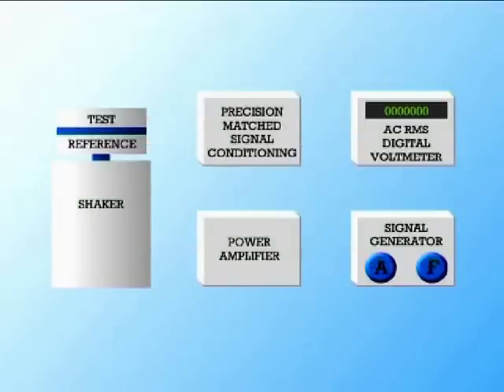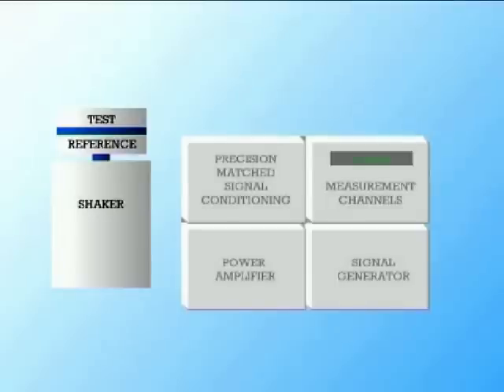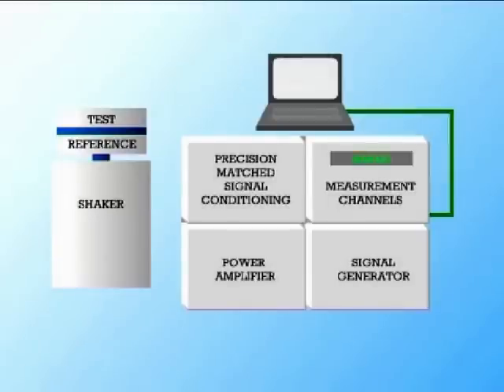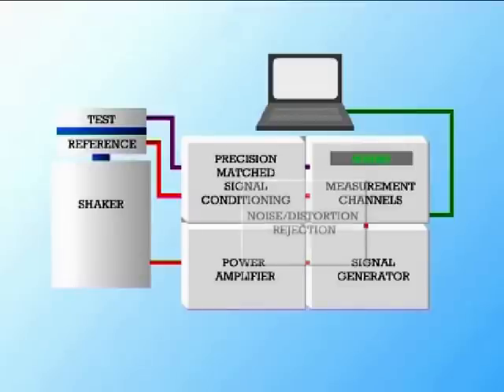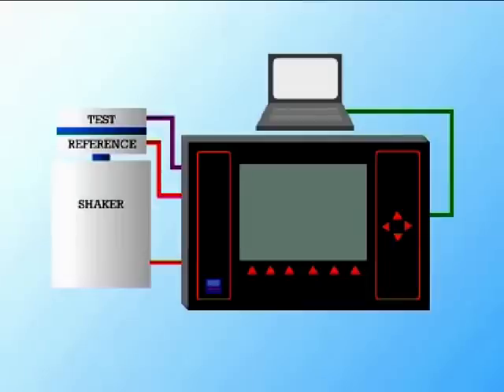The Beran TransCal system automates this whole process, reducing overall calibration time to just 3 minutes per sensor. The same shaker and traceable reference are used, but the individual components are replaced with a single measurement and control unit. The generation of each test frequency and amplitude is automated with a high-speed closed-loop control, and the reference and test sensor signals are now measured simultaneously. The measurement process includes a unique noise and harmonic distortion rejection technique to ensure high repeatability, allowing a rugged and low-cost shaker to be employed in a rigorous industrial environment.